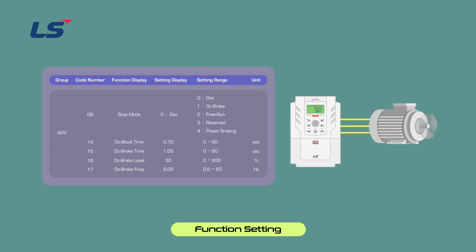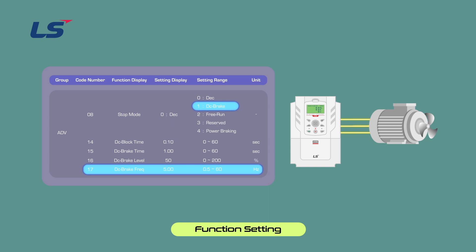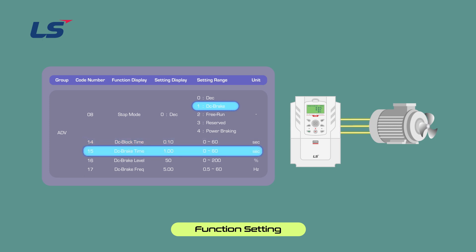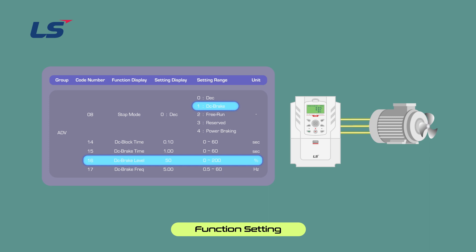The DC Brake stop method is used for high speed spindle motors. Even after stopping, the motor can move slightly due to high speed inertia, so applying direct current braking completely stops the motor. Set 1 DC brake in ADV8 stop mode. When the frequency set in ADV17 DC brake frequency reaches the corresponding level during deceleration, DC voltage is applied to the motor and it stops. ADV14 DC block time sets the time to block the AC drive output before starting DC braking. ADV15 DC brake time sets the time for applying direct current voltage to the motor. ADV16 DC brake level can be set by adjusting the amount of direct current braking based on the motor rated current.